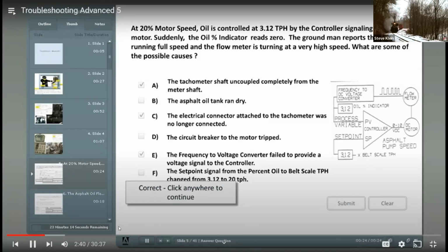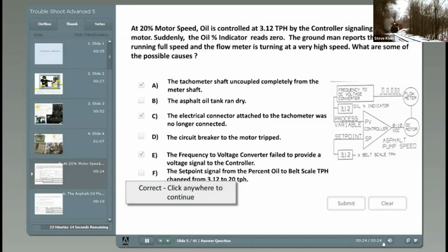A symptom of any output command signal from the controller going to the maximum output, such as 10 volts DC, and the process variable input going to 0, is an indication that something in the electromechanical feedback portion of the closed loop circuit has been broken. The asphalt tank running dry is not an indication because the air being pumped through the meter would turn the meter, but not at full speed, and the oil percentage indicator would be reading some random indication. The motor circuit breaker tripping would not allow the motor to run. The AC oil belt scale circuit is not a candidate because the oil percent indicator would still be reading the oil flow.